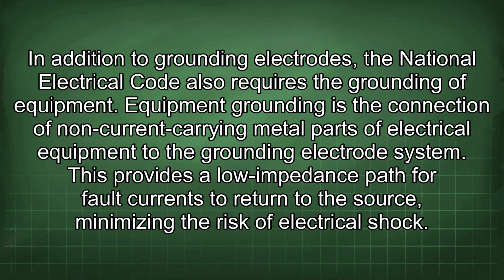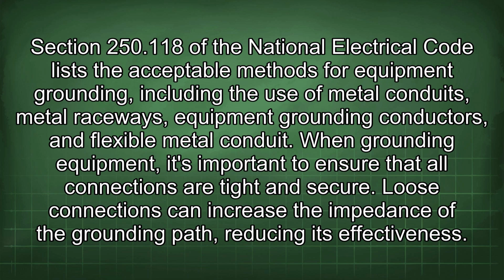grounding electrodes, the National Electrical Code also requires the grounding of equipment. Equipment grounding is the connection of non-current carrying metal parts of electrical equipment to the grounding electrode system. This provides a low impedance path for fault currents to return to the source, minimizing the risk of electrical shock. Section 250.118 of the National Electrical Code lists the acceptable methods for equipment grounding, including the use of metal conduits, metal raceways, equipment grounding conductors, and flexible metal conduit.